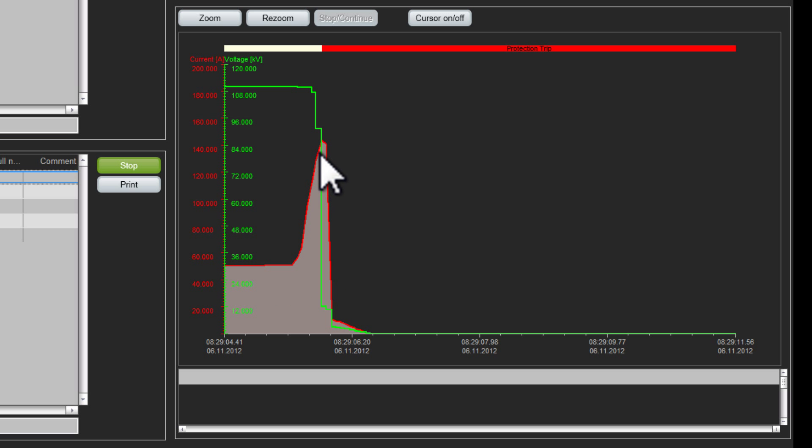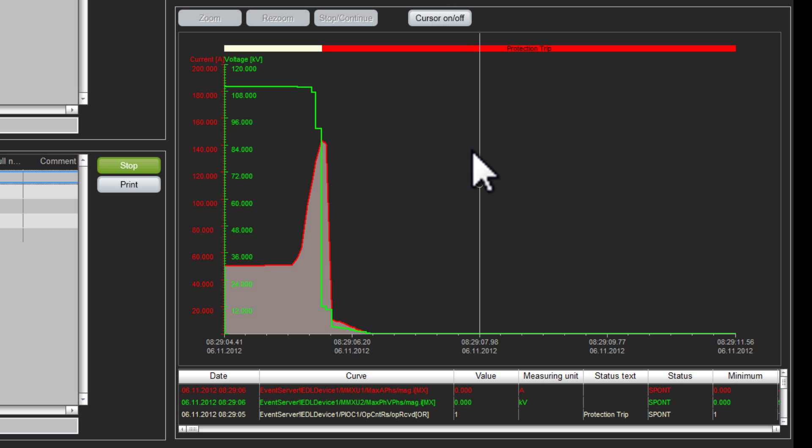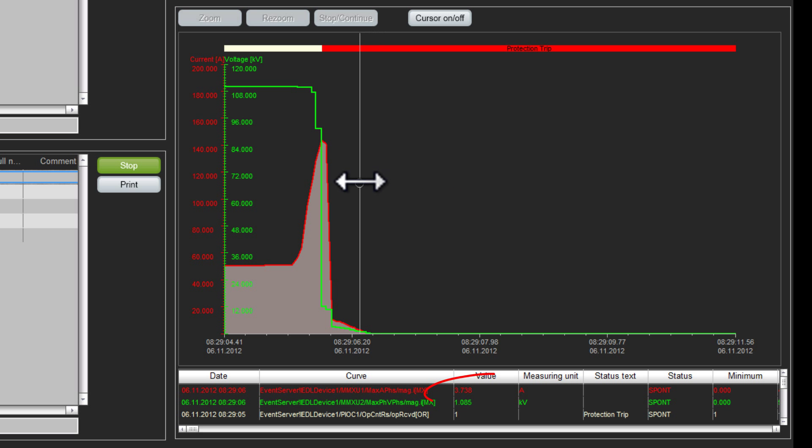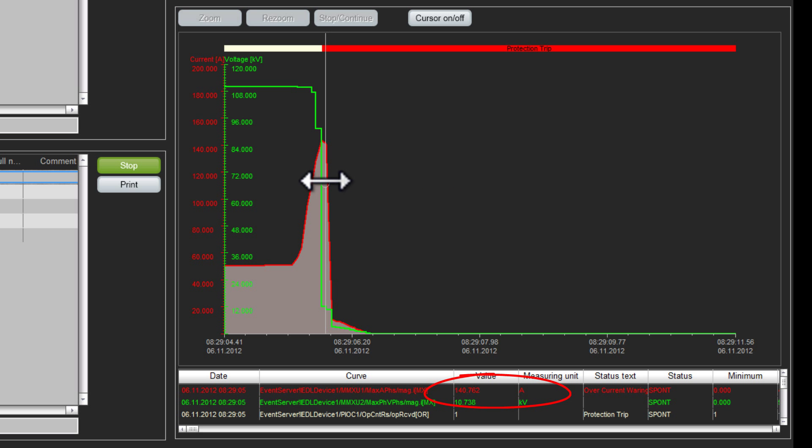I see the current rising and the output of the protection relay. With the cursor I can scan the trend line to learn about the exact amount of amps which caused the trip.